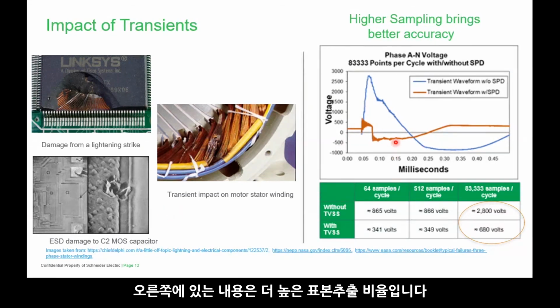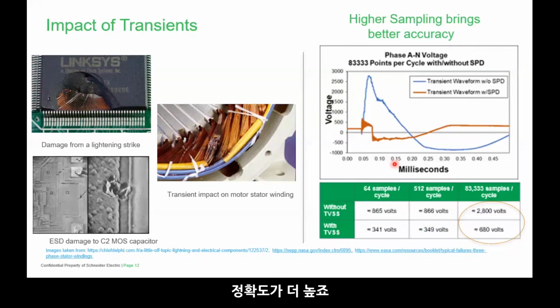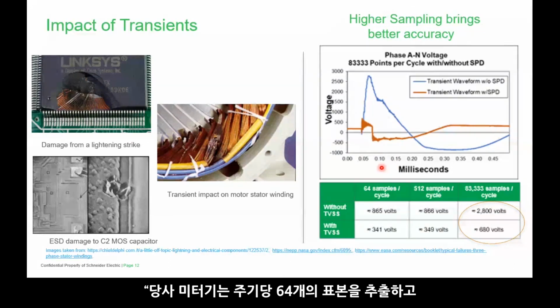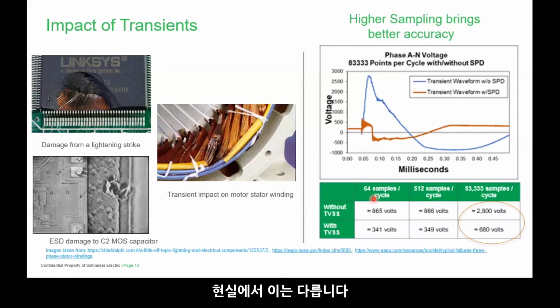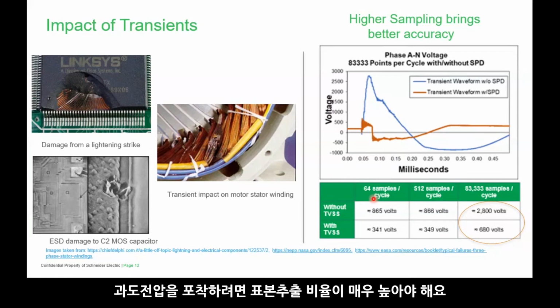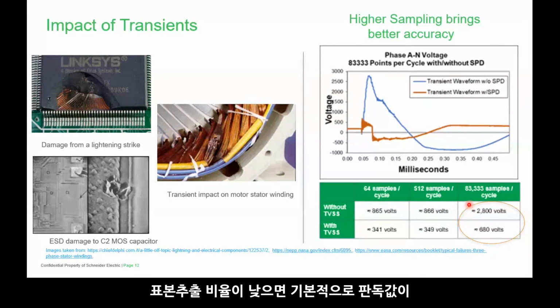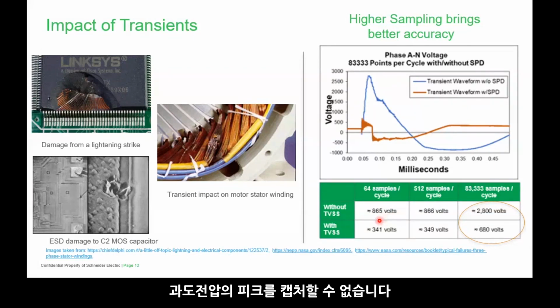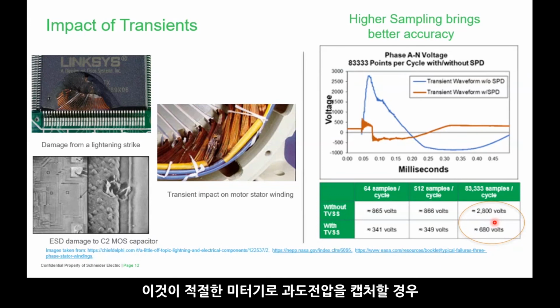Another thing, on the right side, I want to show how a higher sampling rate brings better accuracy. Many metering manufacturers may mention that their meter is 64 samples per cycle and can measure transient as well. But in reality, it's not true, because if you want to capture transient, you really need a very high sampling rate. With a low sampling rate, your readings are not capturing the peak voltage of the transient. For example, with 64 samples per cycle, what you read on the voltage surge is only 865 volts. But with a high sampling rate, you capture the peak of the transient, which is 2,800 volts. This is the data quality you get if you have the right meter to capture transient.